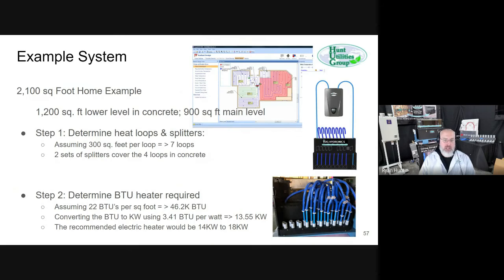Here's a walkthrough that I would do with a contractor, someone who's going to be installing it multiple times, just to understand the process we go through to determine the square feet and then how many pumps it takes to serve those loops, and then the size of the boiler required. Here we're using 22 BTUs per square foot, 46,000 BTUs, and we would recommend our 14. We used to have a 14 kW heater, but we'd probably recommend 18 kW. Now that's the more popular boiler.